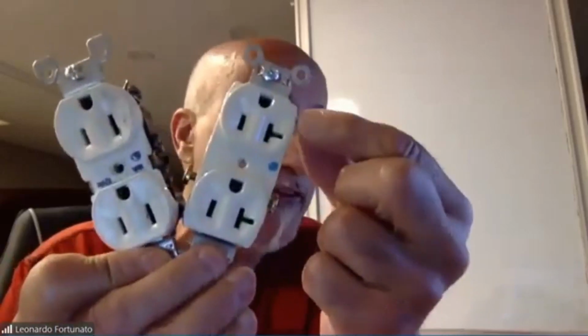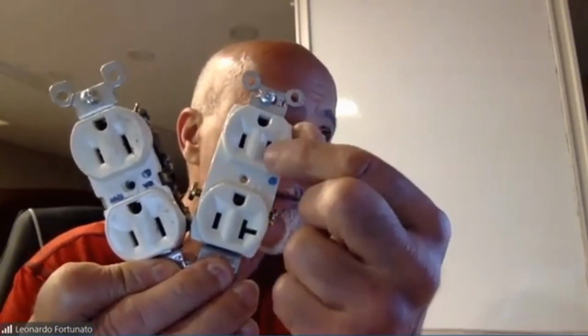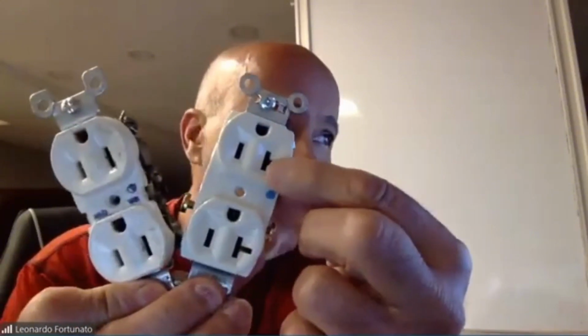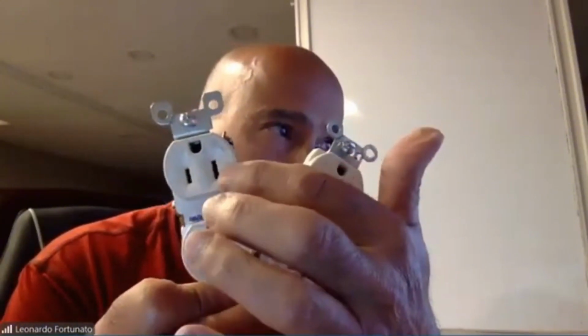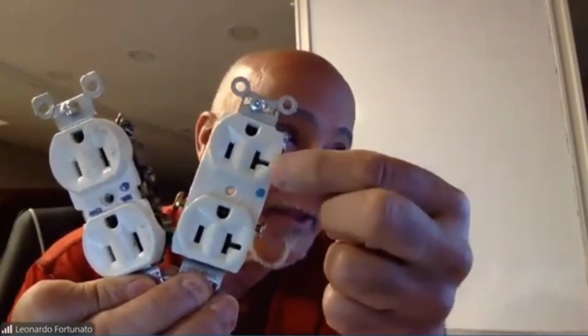When we talk about receptacles, we can have a 15 amp receptacle or a 20 amp receptacle. To make things safer and ensure we're utilizing our equipment properly, a 20 amp receptacle today is going to look like this one here. When we look at the neutral side of our receptacle, that's the longer slot. If you look at the neutral on this one and the neutral on this one, that's just straight. This one is T-shaped. When you see a receptacle with a T-shaped neutral like that, it's going to be a 20 amp receptacle. Fair enough?